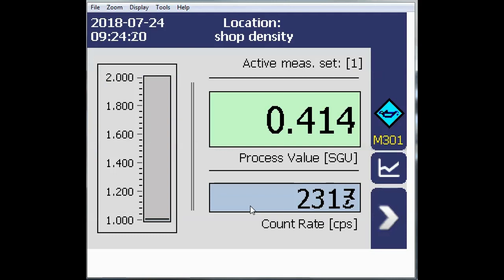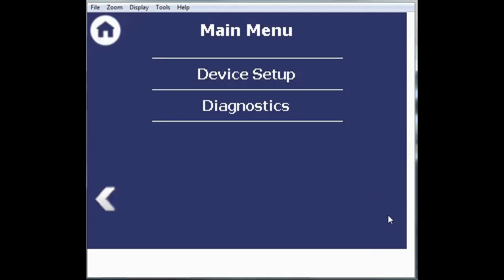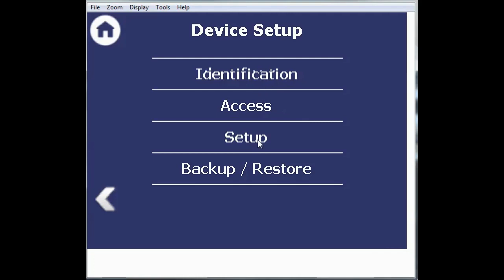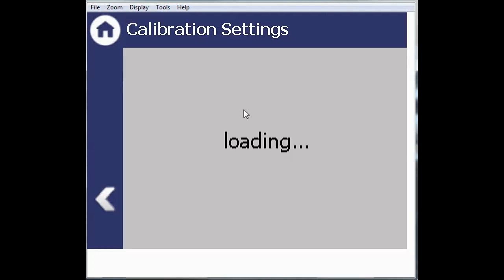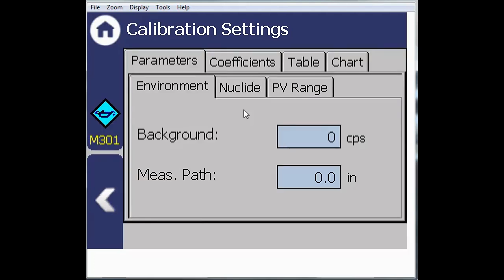So we will begin by selecting the forward arrow in the lower right hand corner and in the main menu. Device setup, setup, calibration, calibration settings. Here we have all the settings for the calibration of your gauge. The background we would only read in if your source has not been installed yet and you're reading true background, whether it be from terrestrial or cosmic radiation. If your source is already installed, simply leave this field 0.